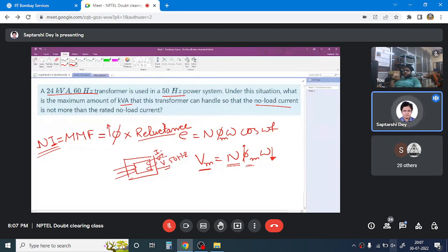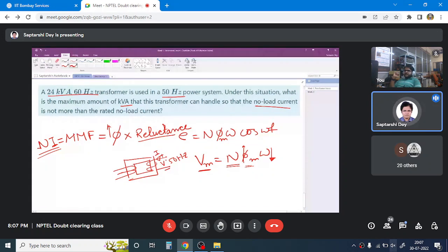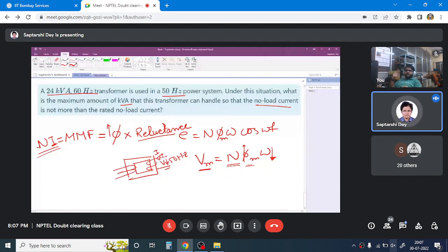Okay. So the no load current has increased. The question is, I cannot let the no load current increase. What do I have to do? The only option left with me is to reduce the voltage. In India, I cannot reduce the power frequency. It is fixed at 50 Hz. So I have to reduce the voltage so that my no load current is equal to the rated no load current. The question is, how much?